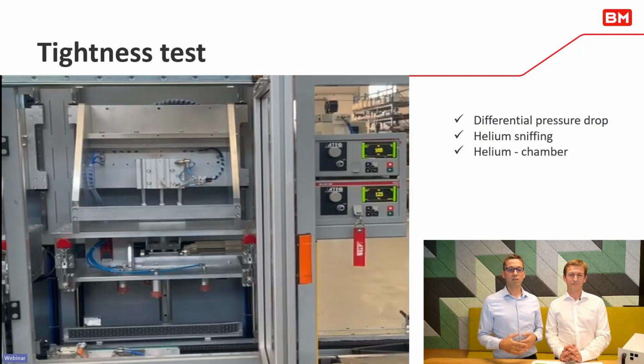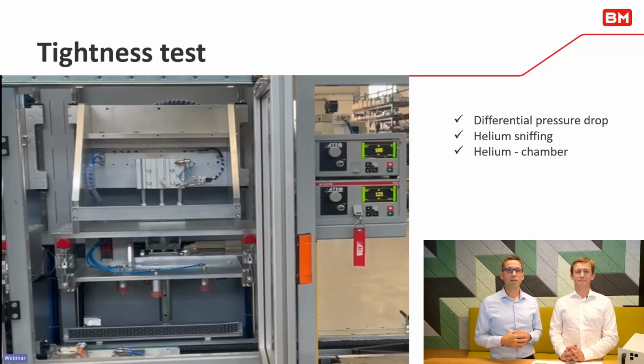Going a little bit more in detail of the tightness test, you can see here a differential pressure drop measurement device where we connect the battery on a plug and make a test setup with a defined pressure. This could be overpressure or underpressure, depending on the requirements, and it can go from -50 millibar up to 2000 millibar, for example. If there are high requirements on the low leakage rate, we can conduct other test scenarios using the helium sniffing method or even a helium chamber, which is more related to the tightness of battery packs with cooling systems.